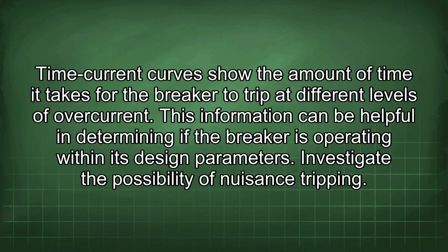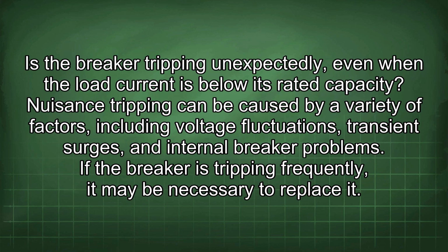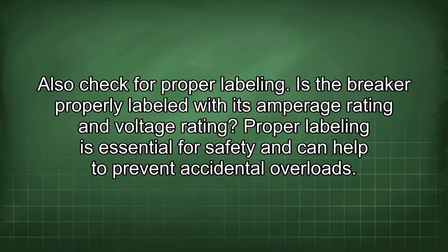Investigate the possibility of nuisance tripping. Is the breaker tripping unexpectedly even when the load current is below its rated capacity? Nuisance tripping can be caused by a variety of factors, including voltage fluctuations, transient surges, and internal breaker problems. If the breaker is tripping frequently, it may be necessary to replace it. Also check for proper labeling. Is the breaker properly labeled with its amperage rating and voltage rating? Proper labeling is essential for safety and can help to prevent accidental overloads.